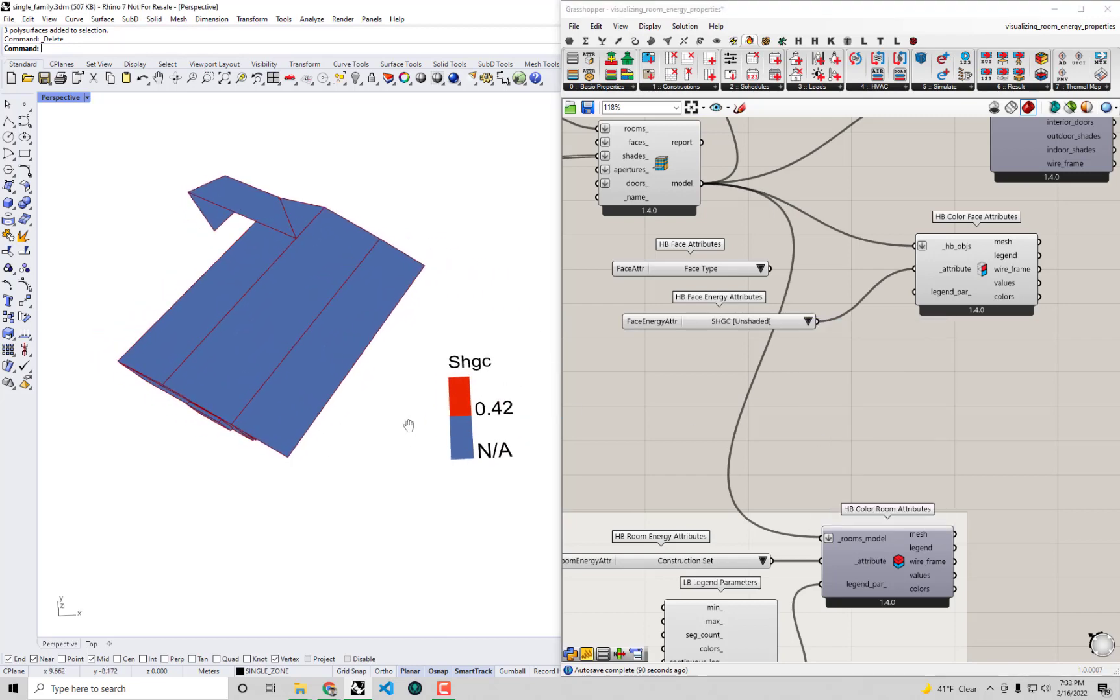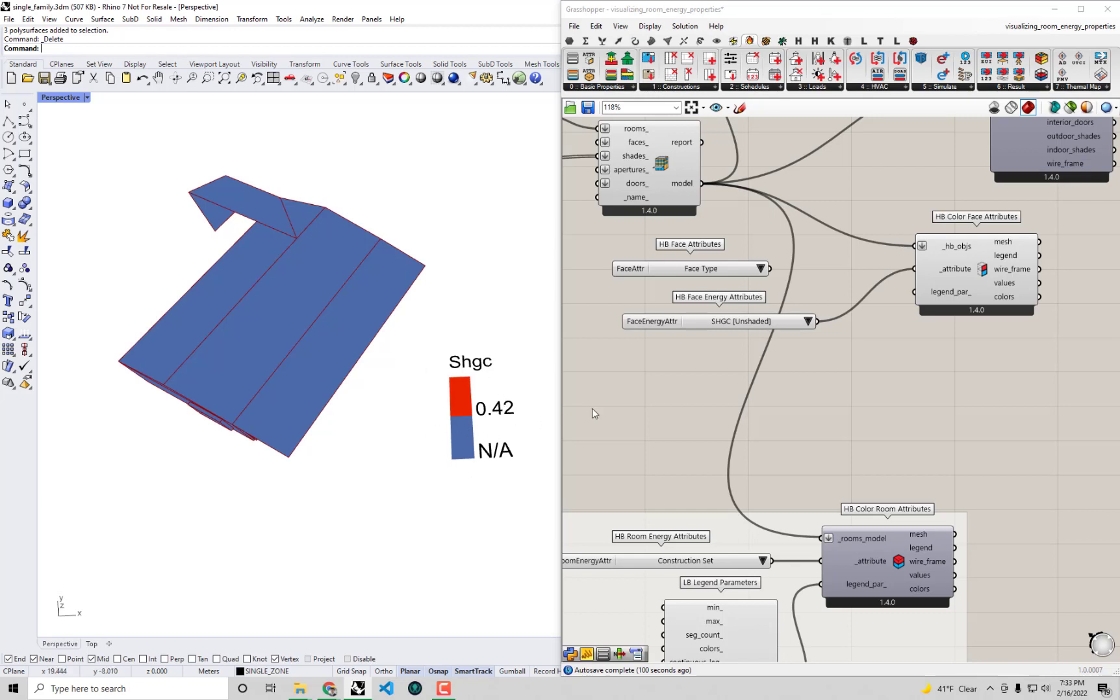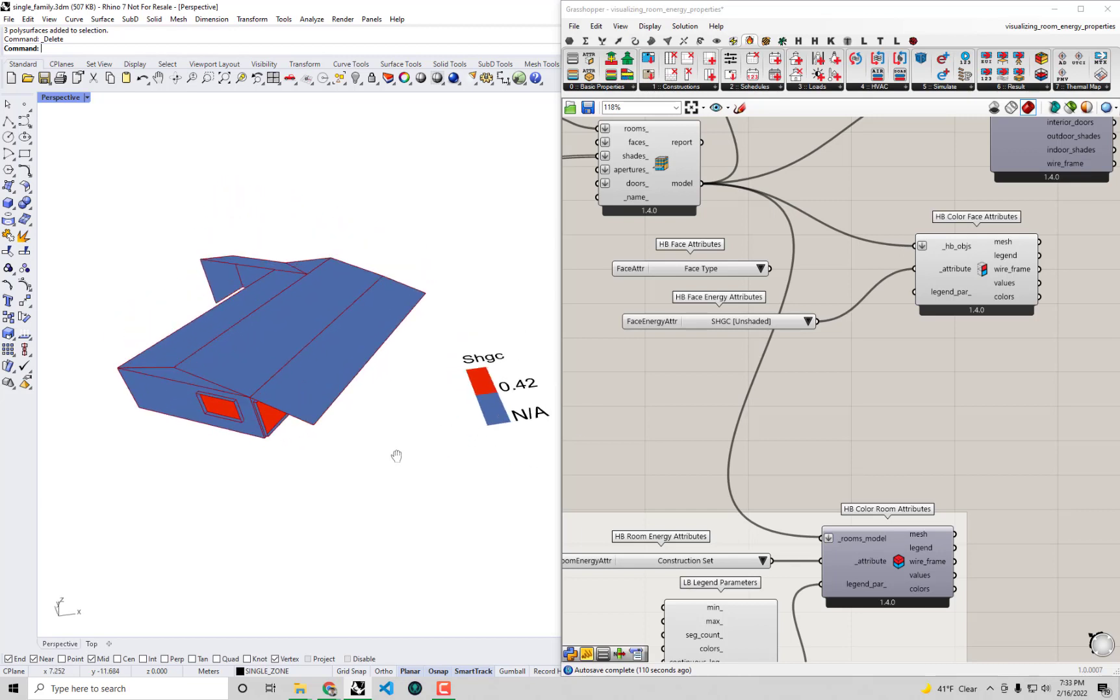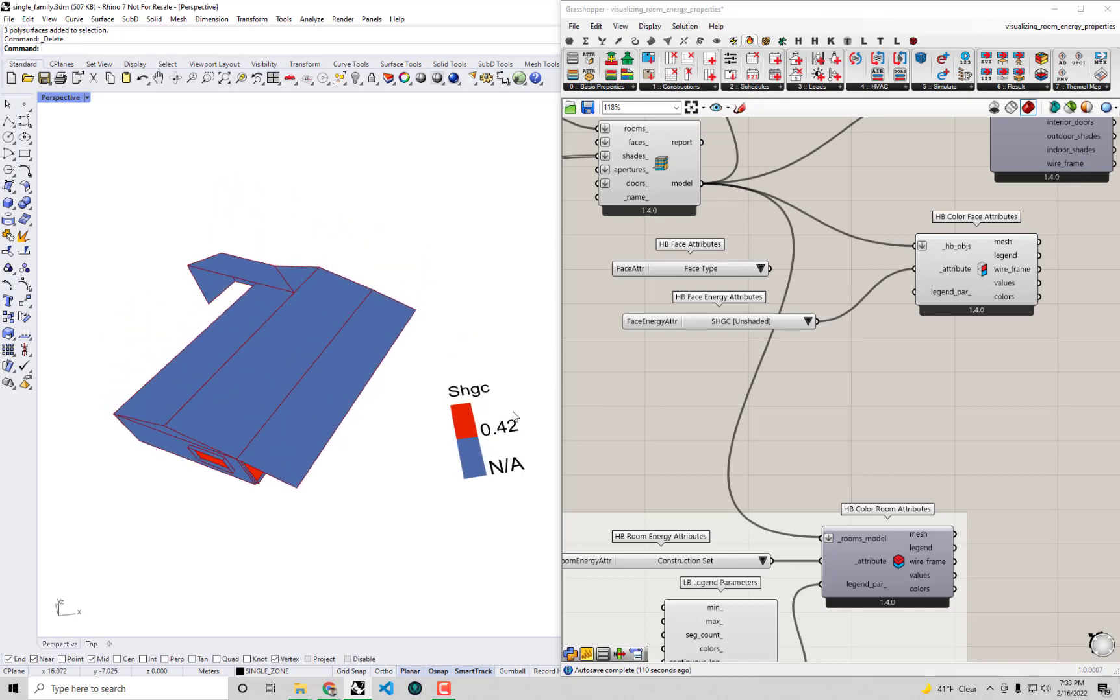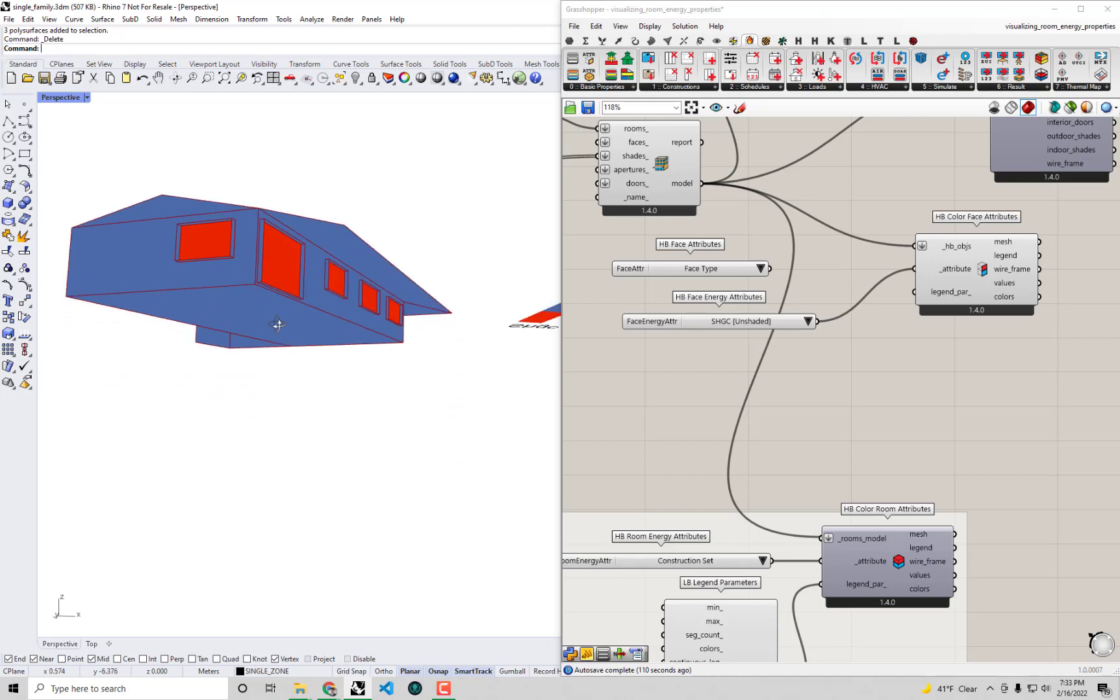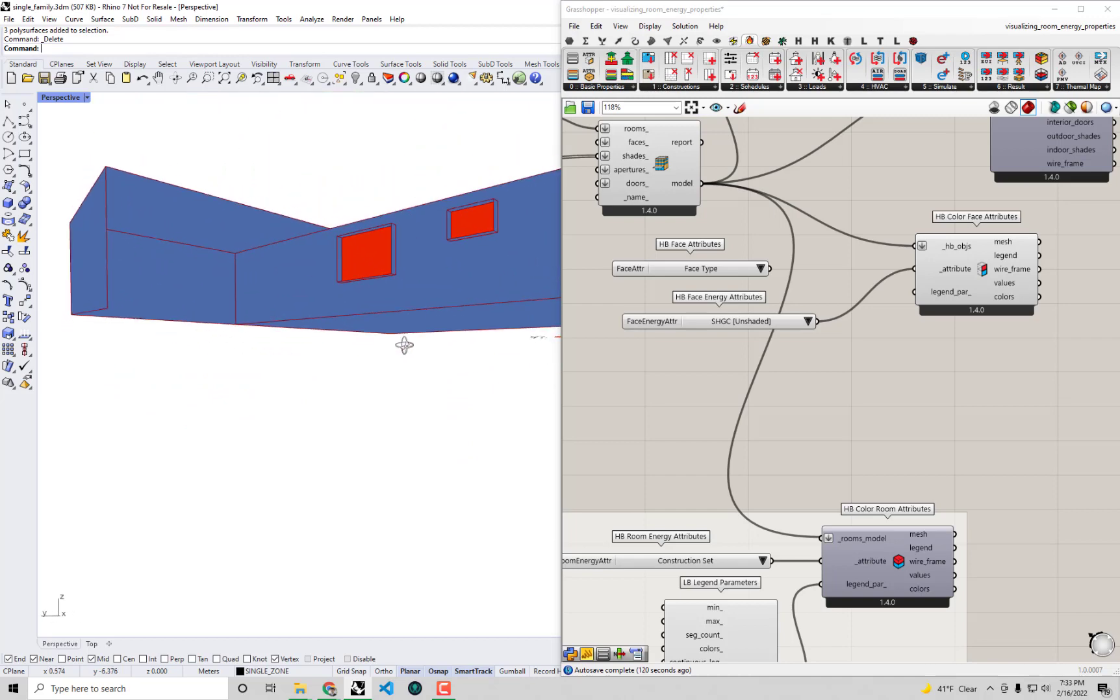Oh this is the biggest red flag I've seen so far. I know my mother-in-law's house is in Southern California and it is very sunny over there. The building code I know for a fact would not let you do a solar heat gain coefficient this high these days. It has to be down below around 0.2 I think, or somewhere between 0.2 and 0.25 is usually where a lot of the solar heat gain coefficients are.